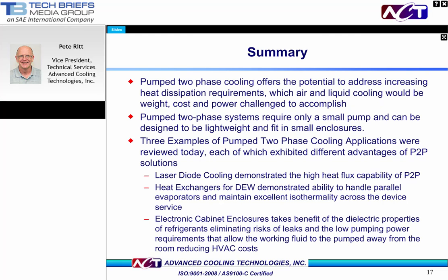And number 3, power electronics and data center cooling, which must maintain high reliability and therefore require the use of dielectric working fluids such as refrigerants. These applications also must maintain tight limits within an environmentally controlled room where the electronics are located. The lower pumping power requirements enable the waste heat to be transported outside the room cost-effectively, allowing HVAC and facility cost reductions. 3 different applications taking benefit of the many features of pump two-phase systems.